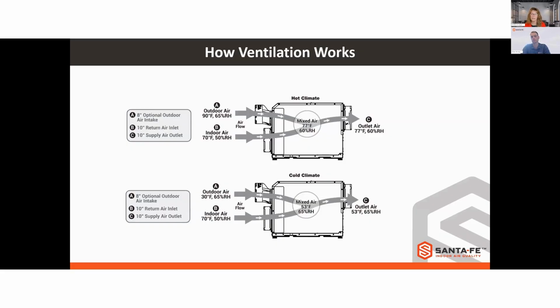Now, if it does come in and starts being distributed throughout the entire house and the relative humidity goes up, then the dehumidifier is going to come on, activating that compressor and removing the moisture from the air. So the ventilation is just based on activating that fan and bringing in that outdoor air. And again, really important, we've got that MERV 13 filter in here that's going to do really good filtration of that air, not only coming from the house, but also from the outside when it is running.